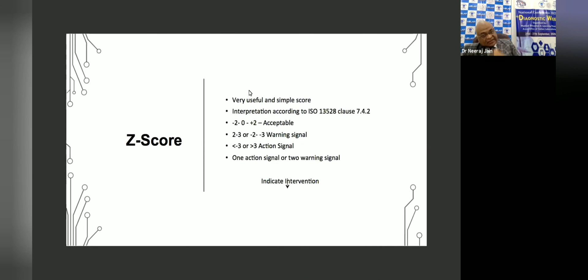And if the Z-score is within minus 2 to plus 2, it is within acceptable limit. If it is 2 to 3 or minus 2 to minus 3, it is a warning signal, and less than minus 3 or more than 3, it is an action signal. 2 warning signals or 1 action signal indicates intervention. We have to see what has happened. With 1 warning signal, we are watching carefully the next run.